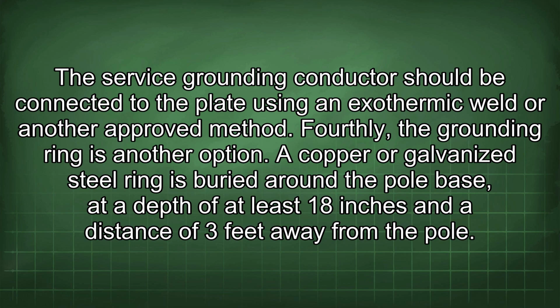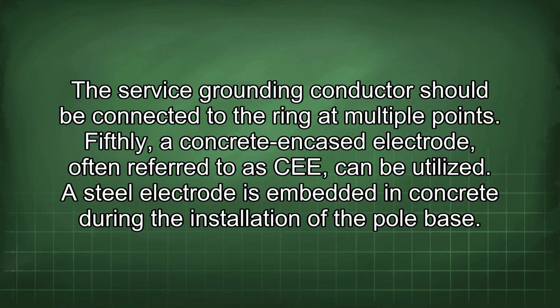Fourthly, the grounding ring is another option. A copper or galvanized steel ring is buried around the pole base to a depth of at least 18 inches and a distance of 3 feet away from the pole. The service grounding conductor should be connected to the ring at multiple points.